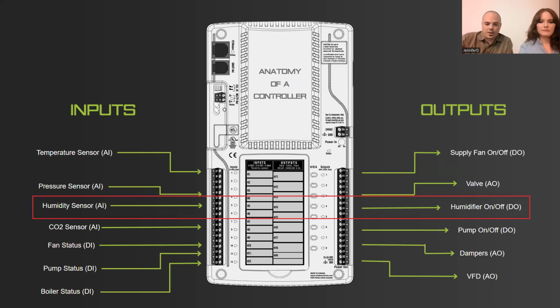We have an output linked to a humidifier command, which is a digital output, on and off. The programming inside the field controller looks at the humidity relative to the set point and says, I need more humidity, I need to command the humidifier to turn on. It turns the humidifier on, and if it's working properly, it'll slowly bring our humidity up until it satisfies that set point.